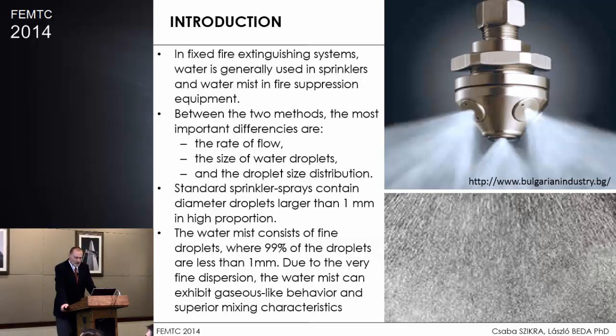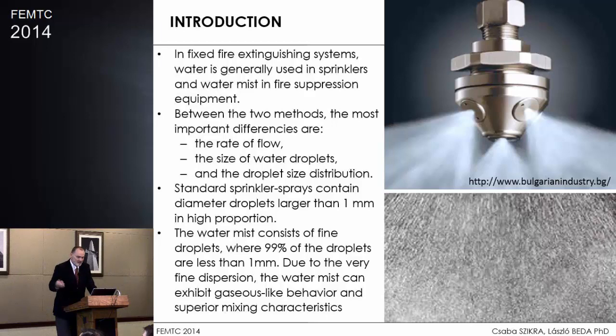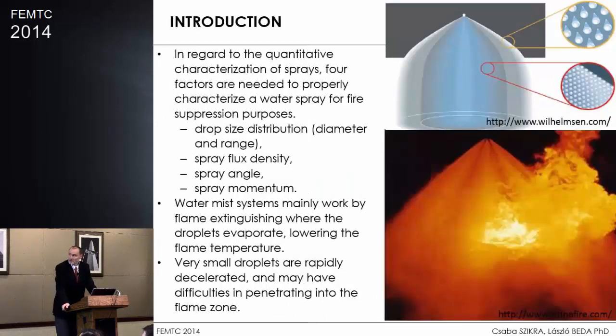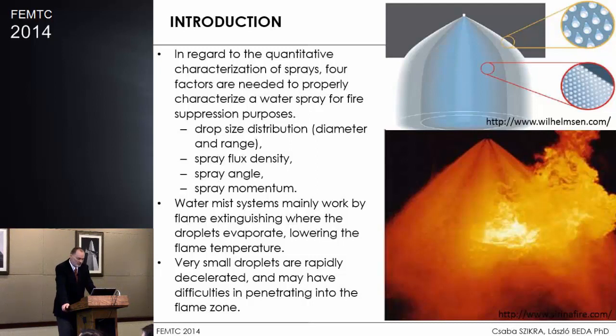Some introductory words: between the two methods, the most important differences are the rate of flow, the size of the water droplets, and the distribution. According to extinguishing efficiency, the size, flux density, angle, and momentum of the spray are quite important. Those parameters have to be set properly during the simulation.